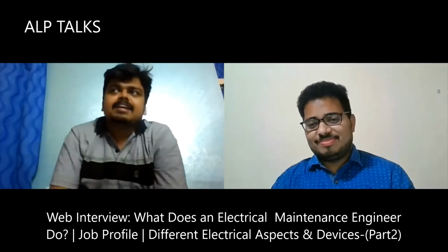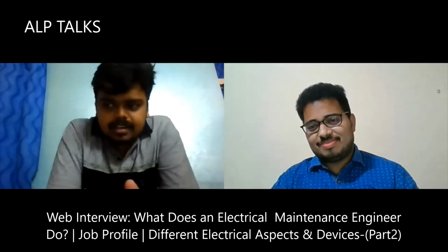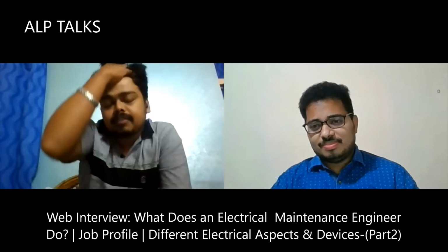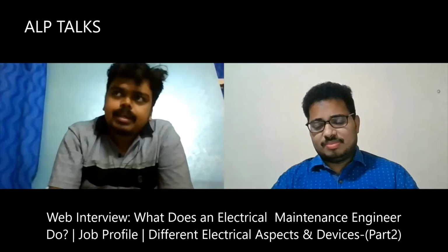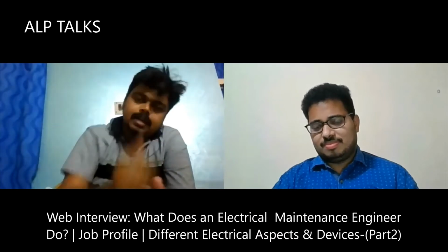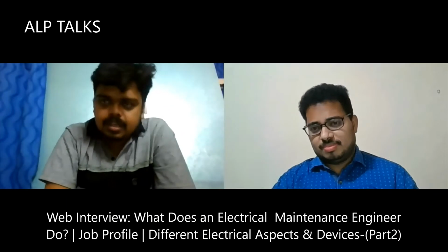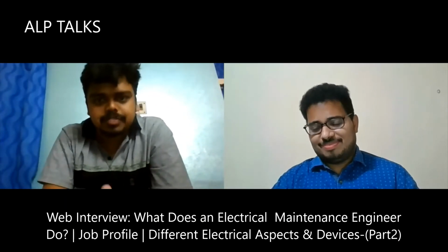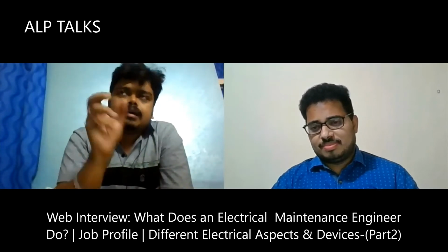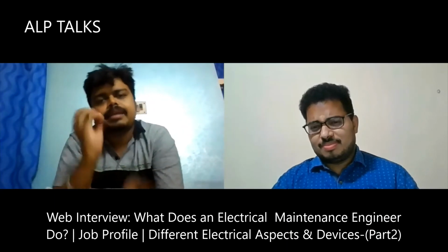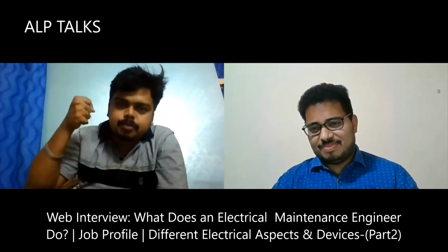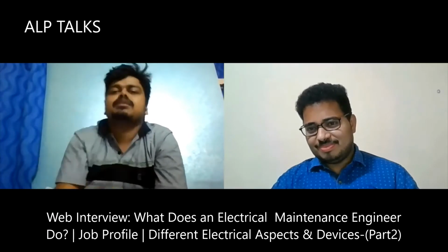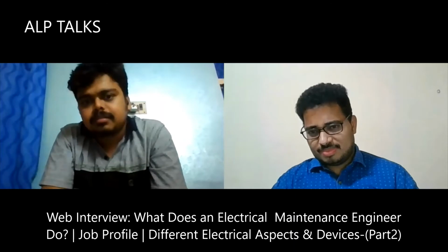The third issue is the differential relay. In our refinery section there's a captive power plant, with substation number 5 and substation number 43. From those substations, incoming 6.6 kV comes in and output is 440 volts. There's a line between SS5 and SS43, and a differential protection relay made by ABB, I think the 615 model. Unusual current surges were triggering the differential relay, and it kept tripping during starting — when SS5 pushed the 6.6 kV voltage, after 1 or 2 seconds the differential relay would trip.